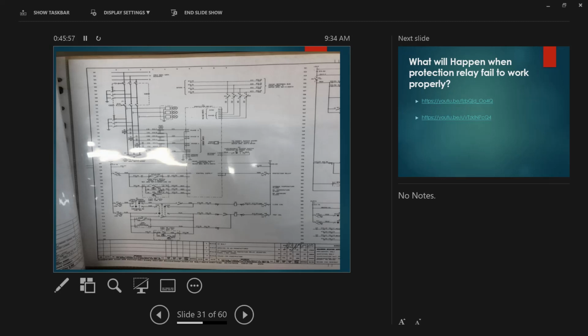At the moment, this one doesn't have the breaker failure because it looks like a feeder. So normally they add some points here saying trip, inter-trip to upstream. Yeah, and there'll be a separate line somewhere in there. Your breaker failure, is that always normally open or can it be normally closed also? It depends on the drawings and the application of the contacts.